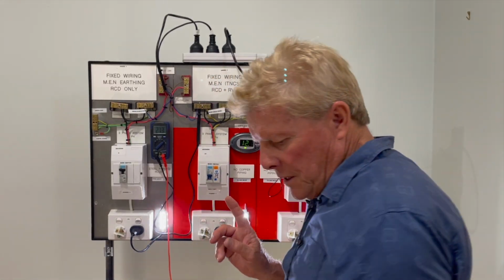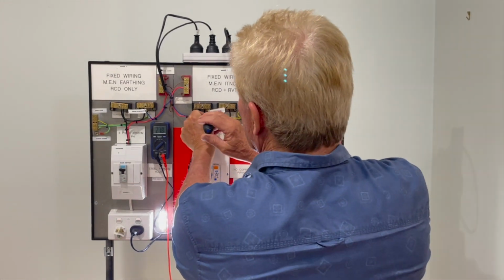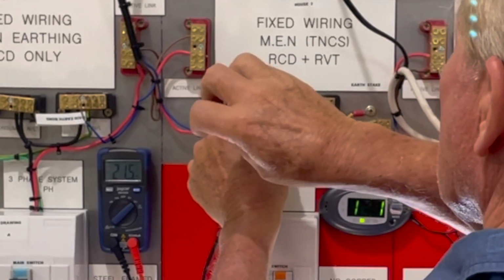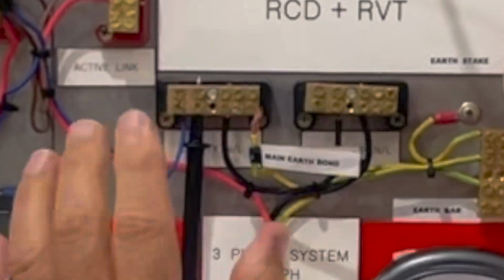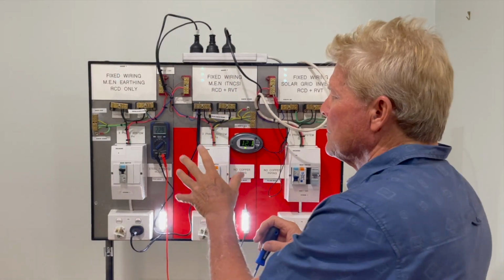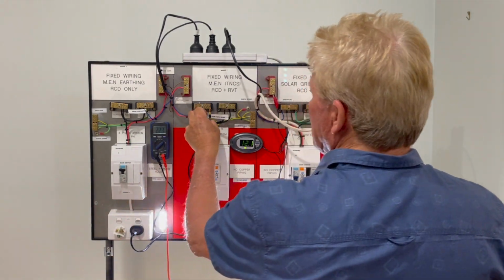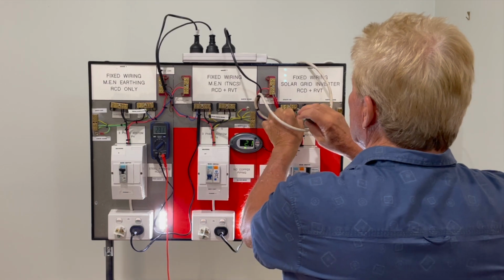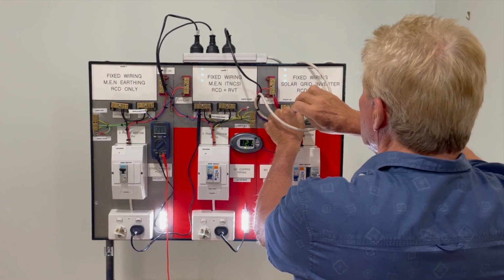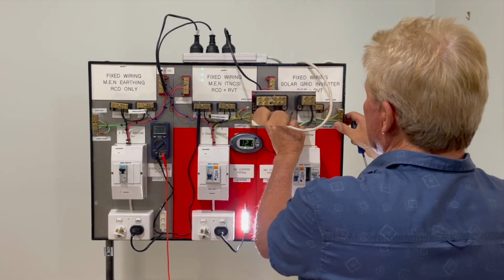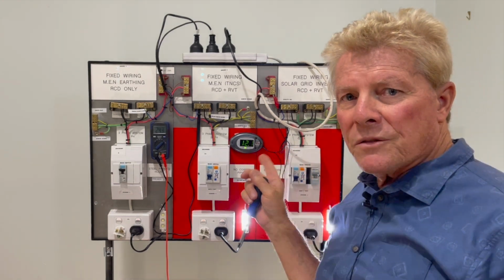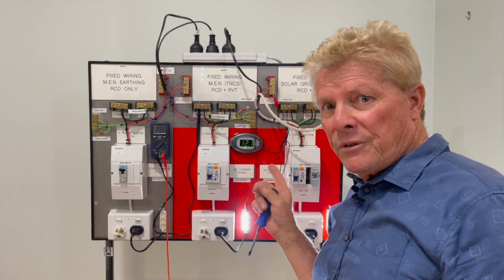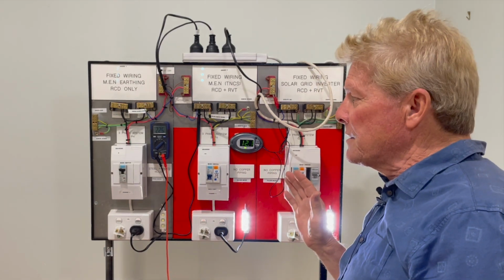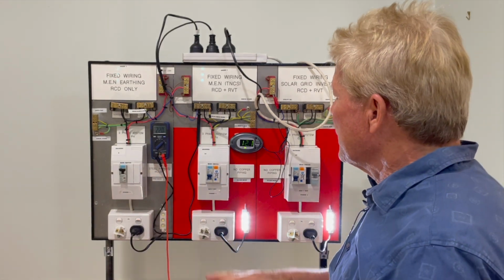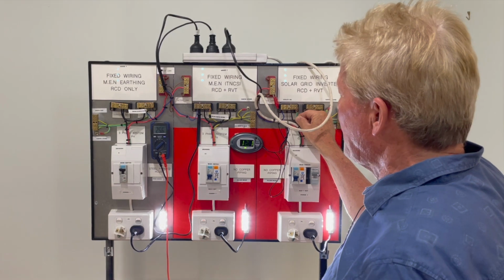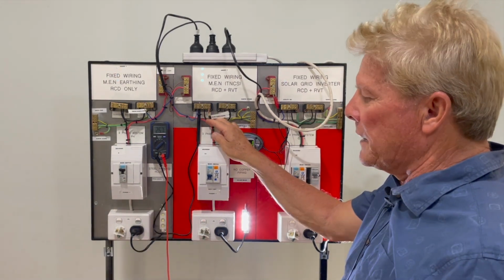So if we disconnect this main earth on house 2, this is just confirming the ring circuit on the neutral, and nothing happens. If we lose the earth on house 2, nothing happens. See what happens when we lose the earth on H3, house 3? That's C phase on a 3-phase distribution system. That's 120 degrees from this house over here. And when I tap that one or tap that one, we get power back here.